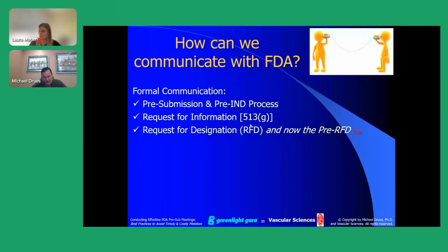I had a situation about a year or a year and a half ago where we did a 513(g) request. The FDA came back and said, yes, this is the way it is. Then we subsequently did a pre-sub, and FDA said, oh, we're sorry, but we changed our mind and we're no longer sticking with what we told you in the 513(g).